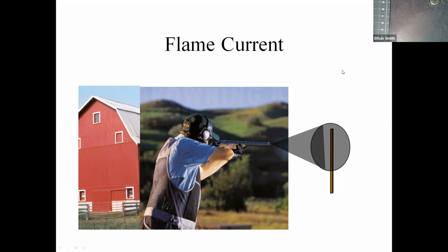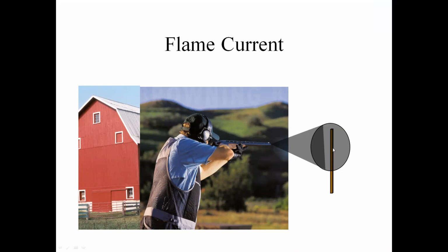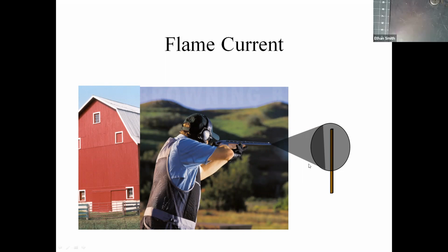But basically that's what the control board is doing, is we're taking that flame sensor and we're manipulating it so that we have as much current passing through the flame sensor to ground as we can. So that's why you see flame sensors not posted right in the middle like this one is, but off to the side so that they can pick up more of the perimeter of that flame current. Ideally, you'd have your flame sensor cut right through the edge of the flame to pick up as much of that actively burning flame as you can to get as high a flame current as you could.